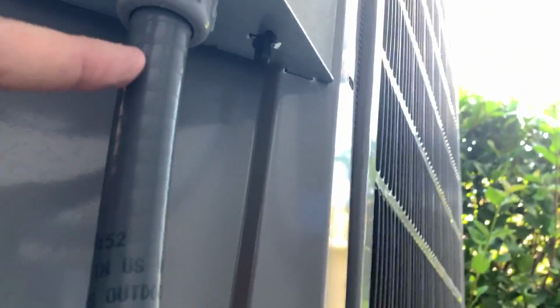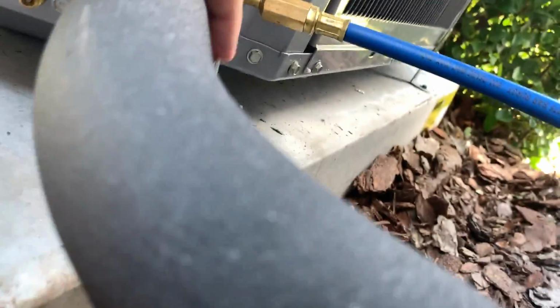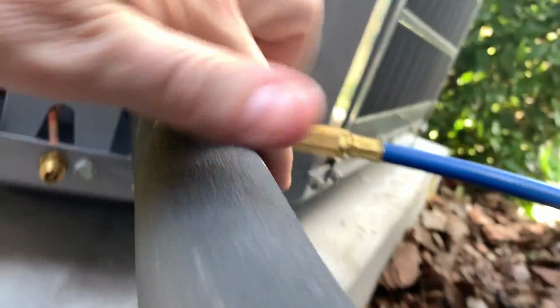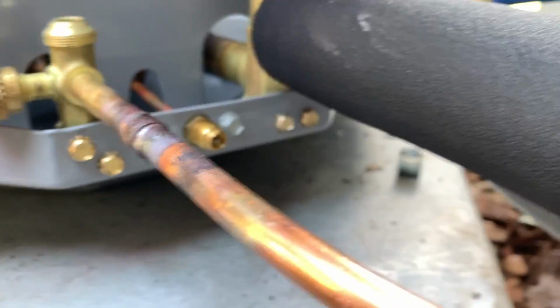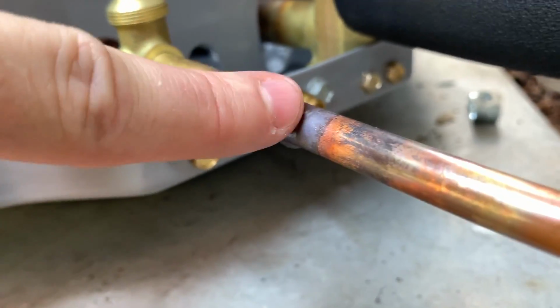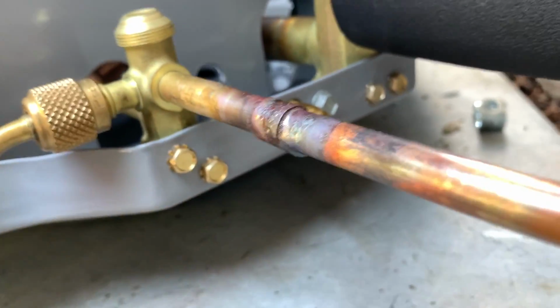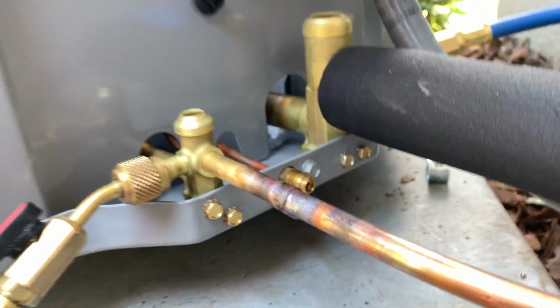So Manny is now using Seal Tight even on low voltage, which, you know, some places they've done that forever. In Florida, for whatever reason, we haven't done that, but this is definitely what we're doing from now on. Bringing the Seal Tight Carflex, whatever you want to call it, on the low voltage line as well. Looks really sweet, so well done there. Nice looking joints, very pretty. Well pulled in. You can see you actually heated it up properly, so it actually drew that alloy into the joint just like you're supposed to.